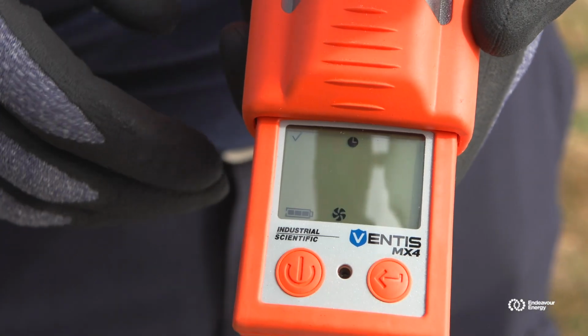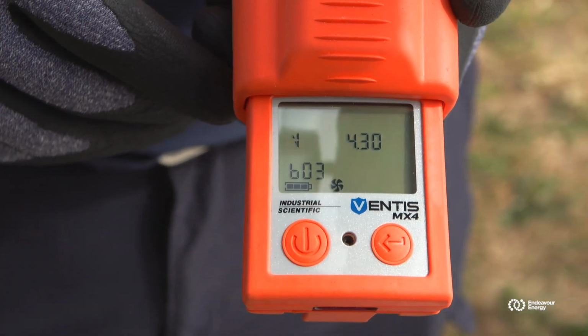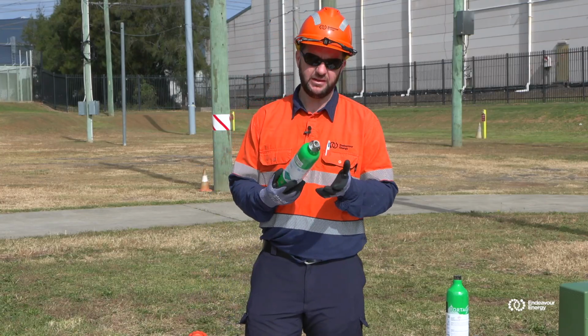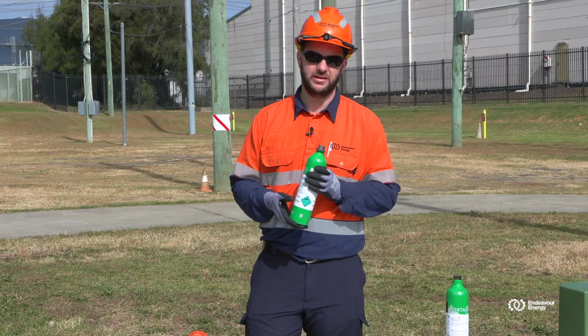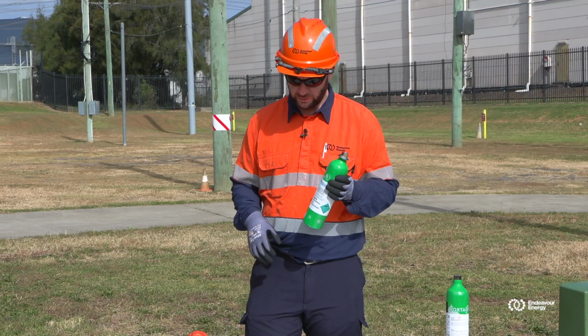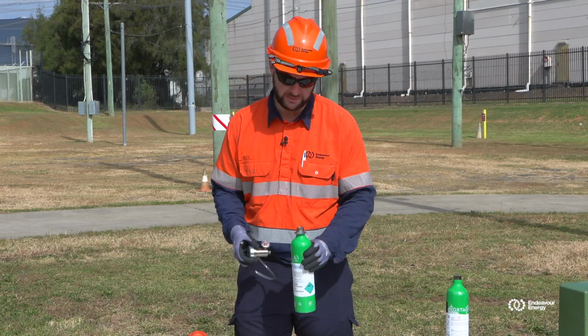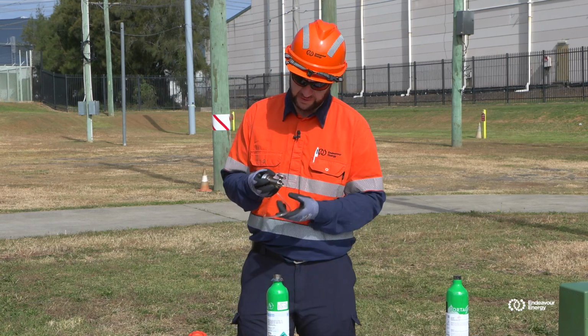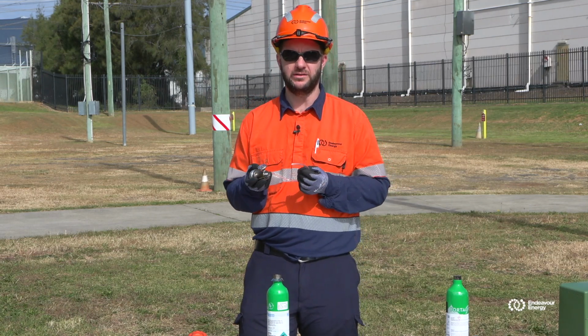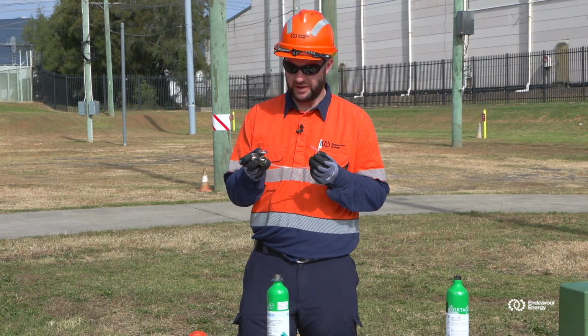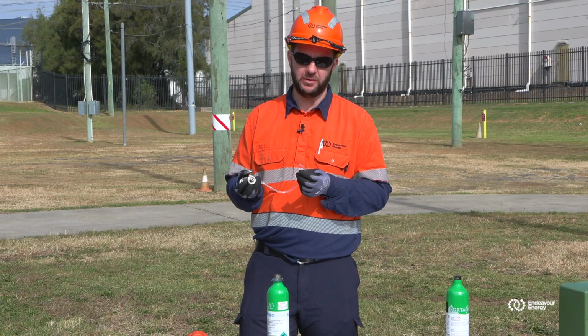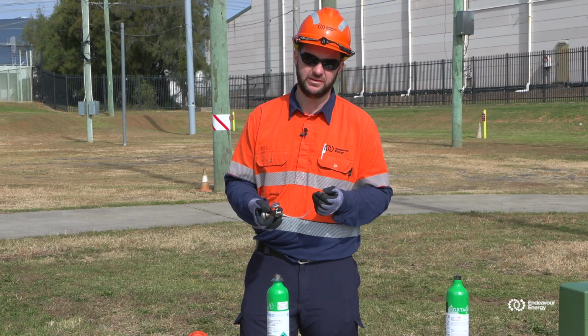While that's happening, I'm going to have a quick talk to you about the test gas bottles we use. So these are the test cylinders which we're using to test the gas detector. As well as using them, you may have two different types of regulators. This particular regulator doesn't have a valve which requires us to open and close. It's activated by the pump, so once the pump starts sucking, it'll pull the test gases out of the cylinder.